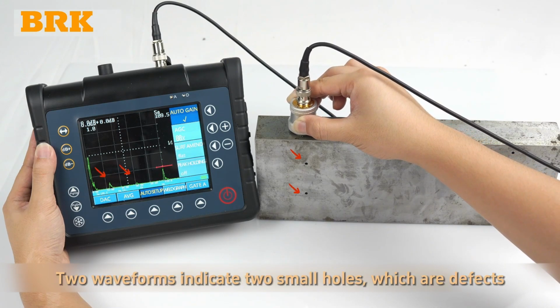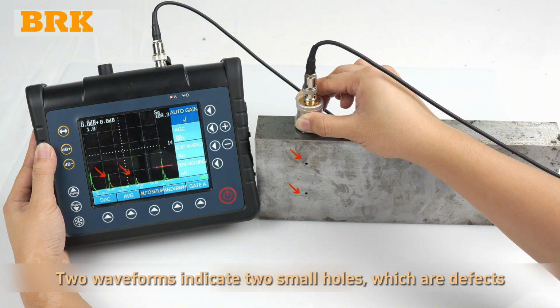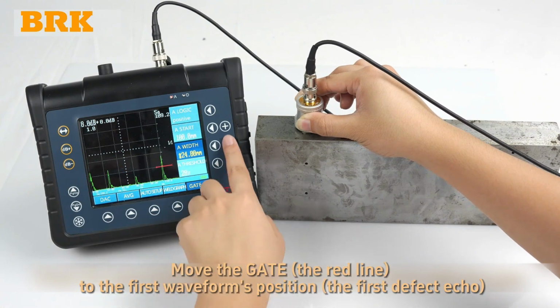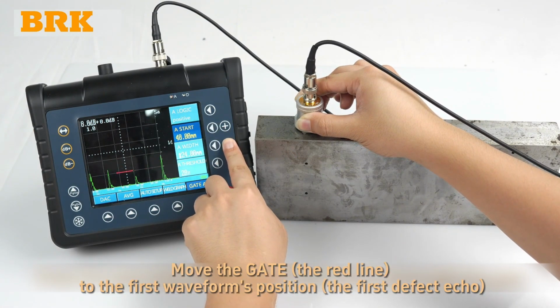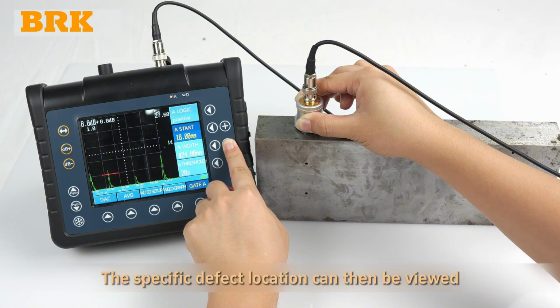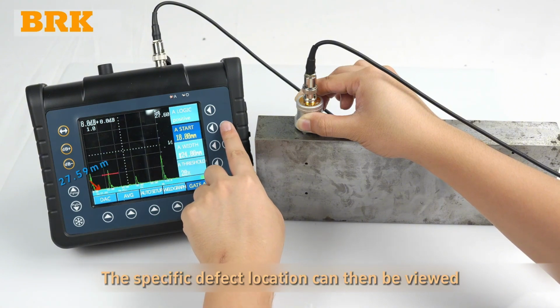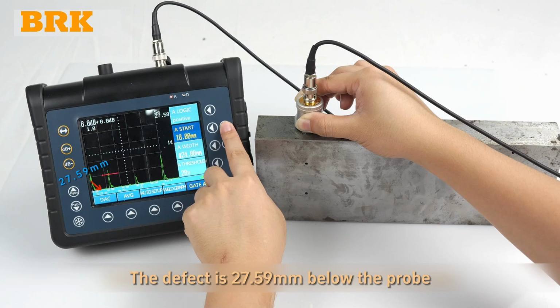Waveforms appear. 2 waveforms indicate 2 small holes, which are defects. Move the gate to the first waveform's position. The specific defect location can then be viewed. The defect is 27.59 mm below the probe.